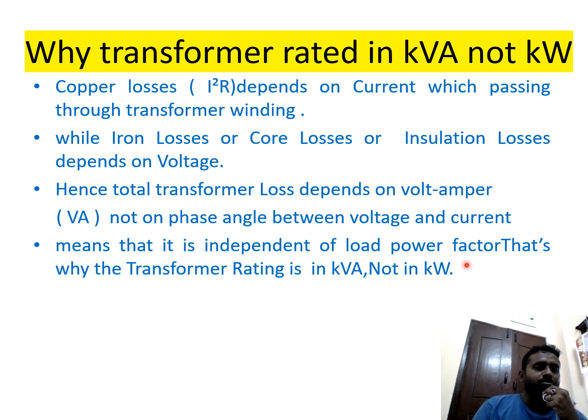Transformer is a device to which any load can be connected with some power factor, so it should be able to provide sufficient current and voltage to the connected device. So it's actually rated in kVA, kilovolt ampere, not in kilowatts. The basic difference between these two, kVA and kW, is the power factor. Power factor is existing in kW and power factor is absent in kVA, the simple point.